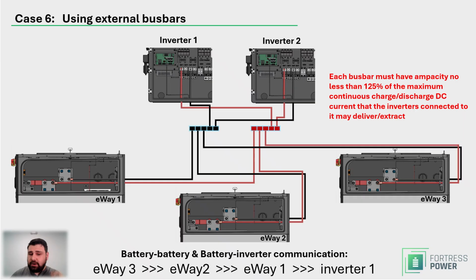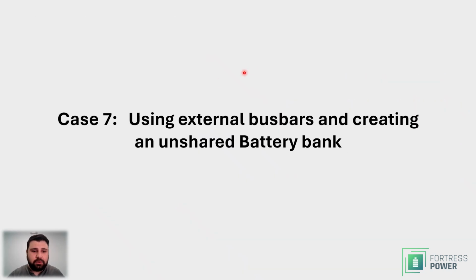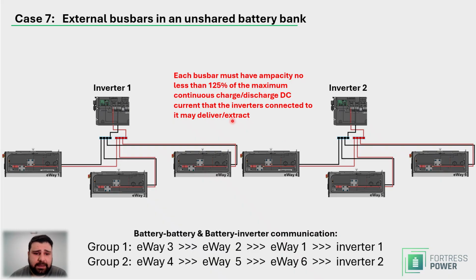But now that you know how it is for unshared battery banks, let's combine the unshared battery bank knowledge with the external busbar understanding and get to our bonus case, which I mentioned before, using external busbars and creating an unshared battery bank. This is what it looks like. So you have inverter 1, inverter 2. You have a group of batteries for inverter 2. You have a group of batteries for inverter 1. And it could be 5 batteries, 6, all the way up to 28, really, technically. That's how much we can cover with our communications, 28 batteries in one communication chain.